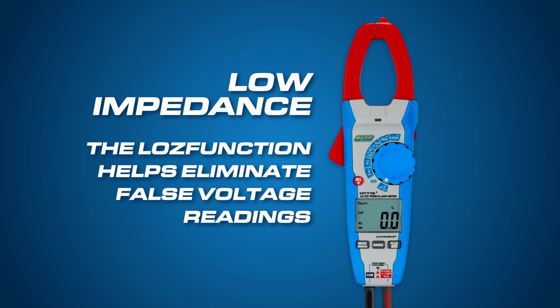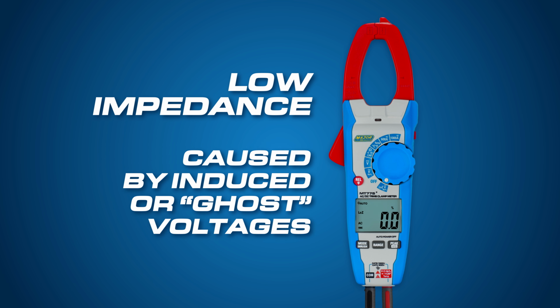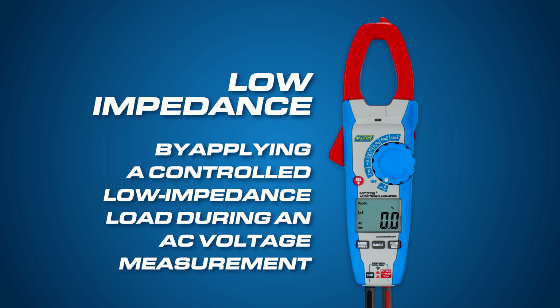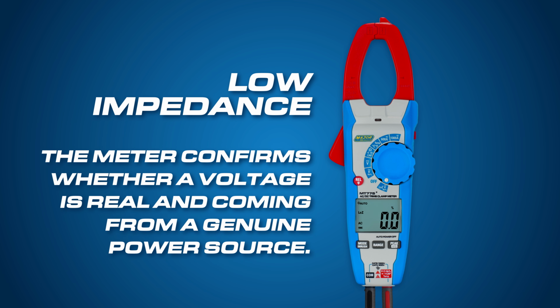The low input impedance function helps eliminate false voltage readings caused by induced or ghost voltages by applying a controlled low impedance load during an AC voltage measurement. The meter confirms whether a voltage is real and coming from a genuine power source.